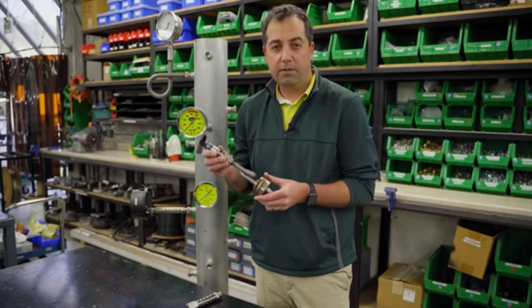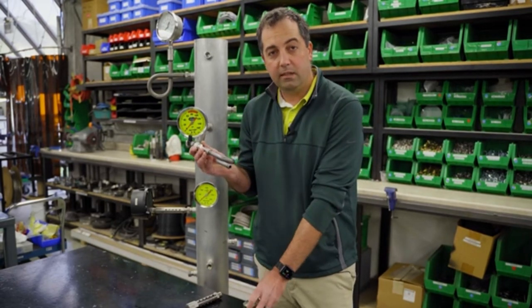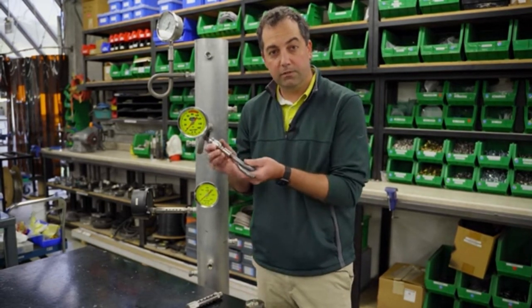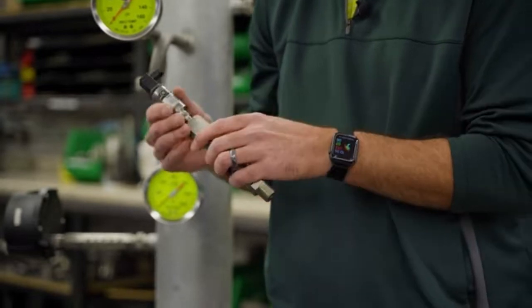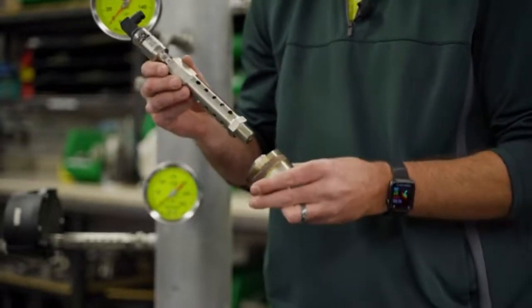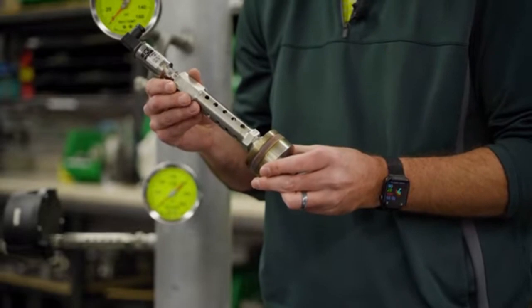No, siphons have far too large of an ID, introducing unnecessary fill fluid into the diaphragm seal system, which will affect accuracy. Go with a cooling element instead.